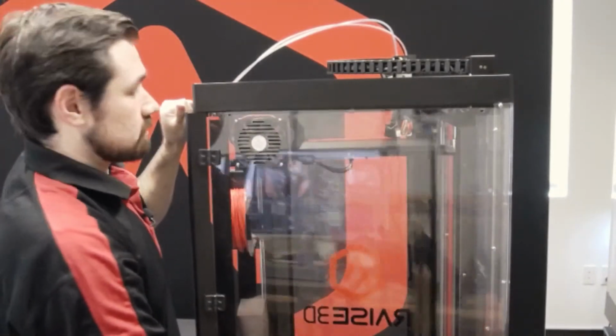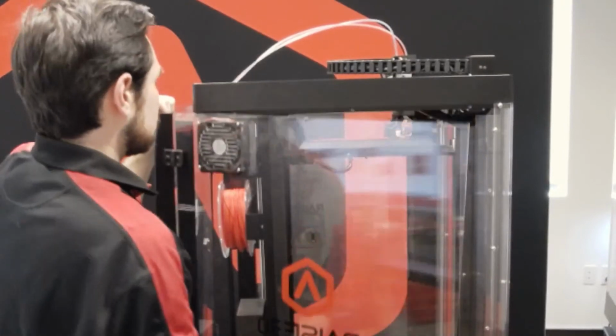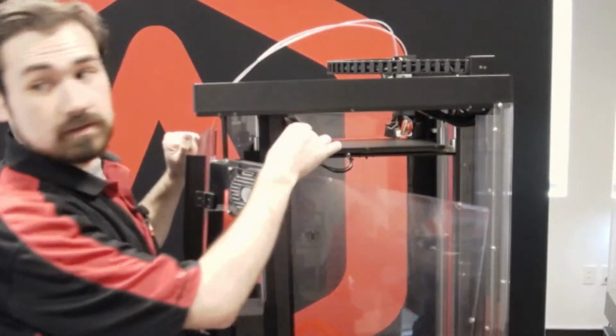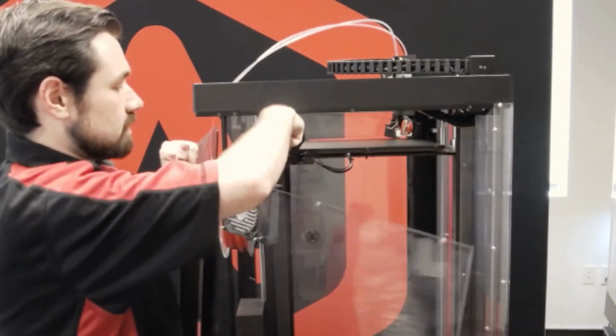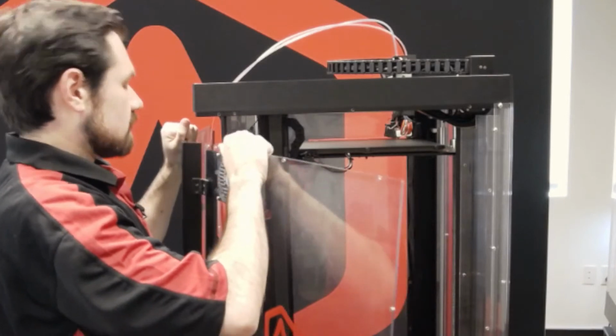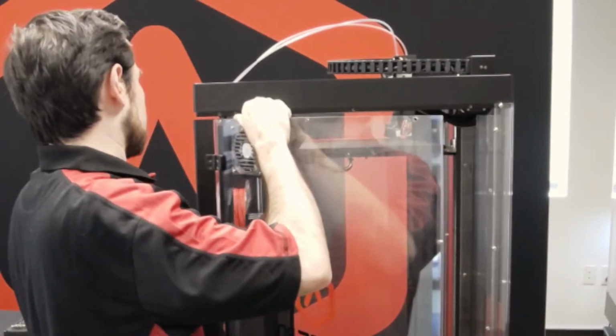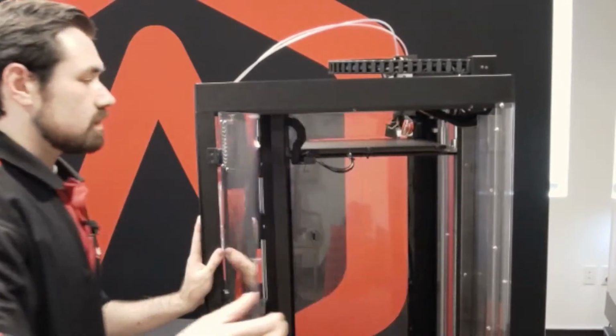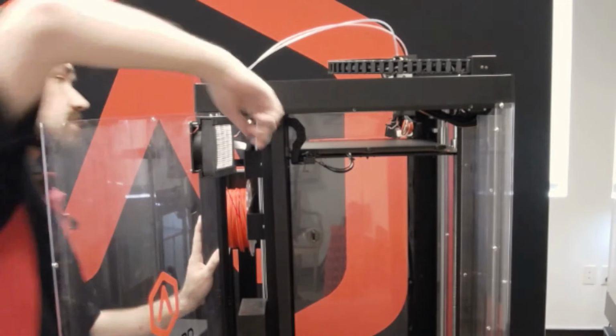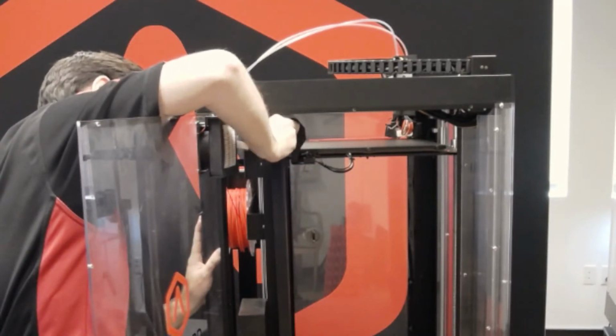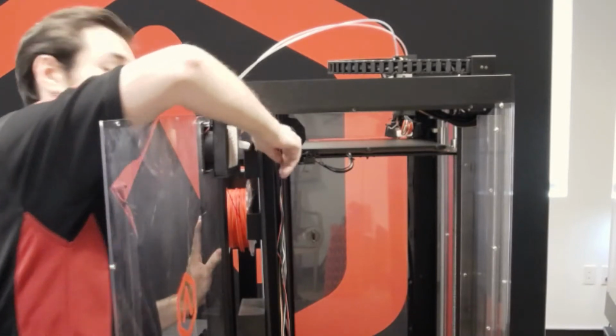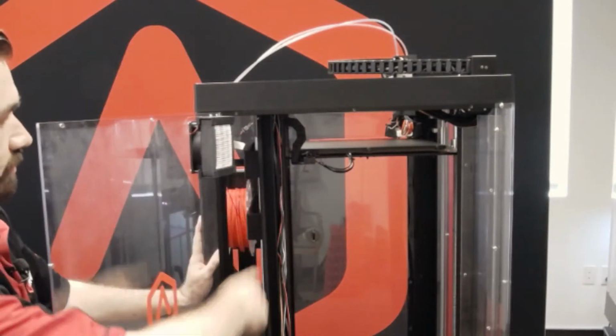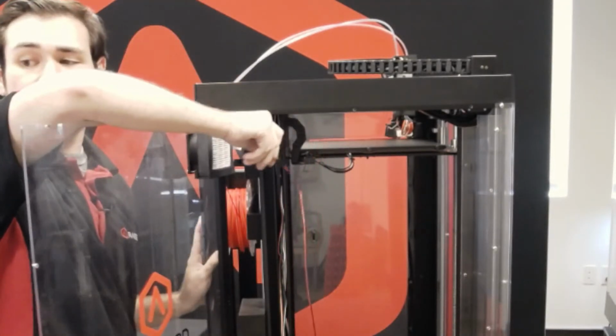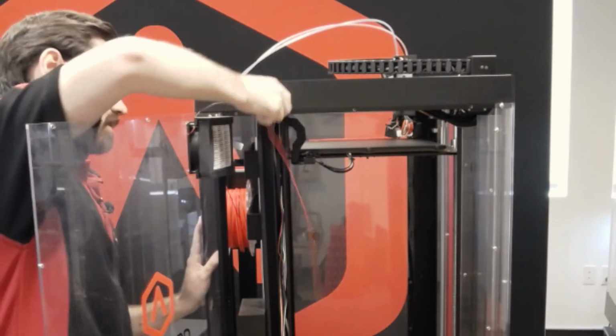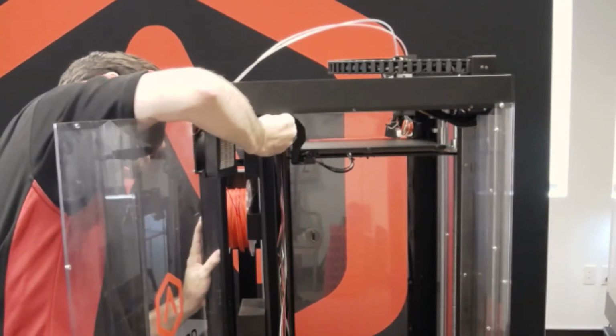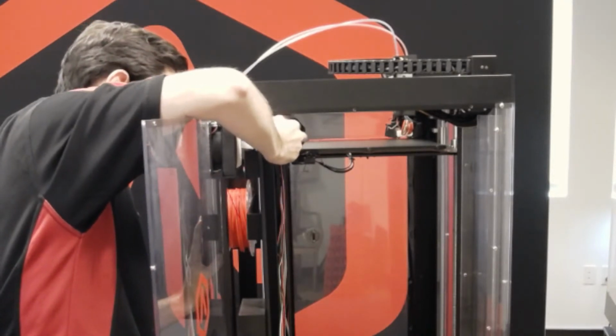You do want to be kind of careful. I haven't fully pulled it out yet because of the HEPA filter cable. This cable runs directly into this back channel. In some cases, if the HEPA filter cable is typically an older cable, it will run down the entire length of this. So we may need to open it up and expose the entire cable channel and uninstall the connection somewhere further down in this. Some of the newer HEPA filters have the connector up in here, so I can actually just deal with that connection rather than needing to go through the entire cable channel.